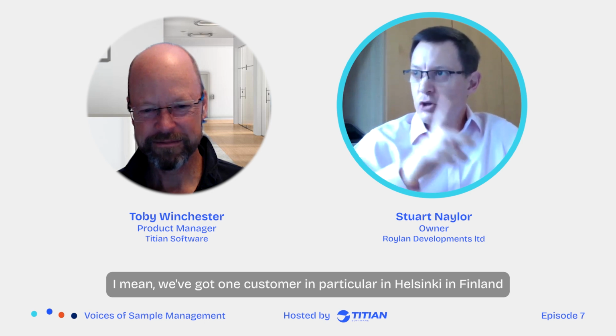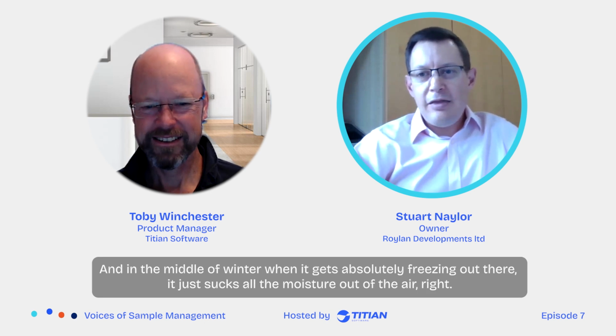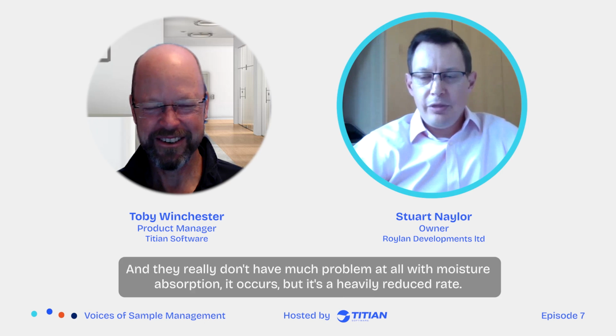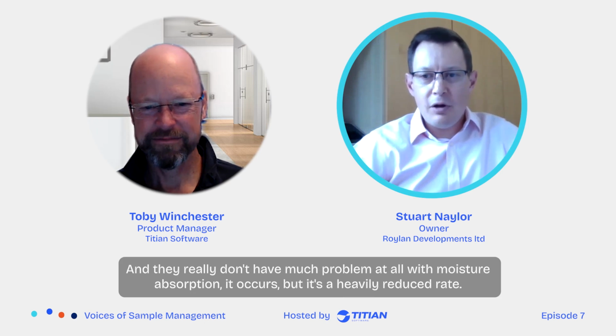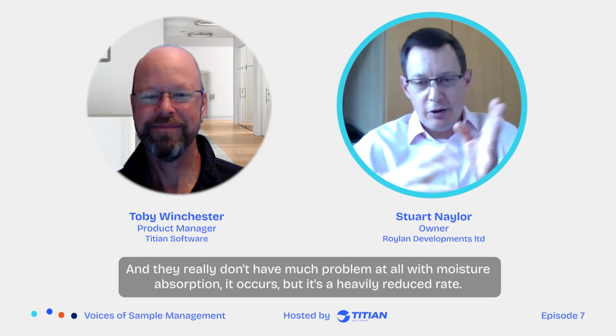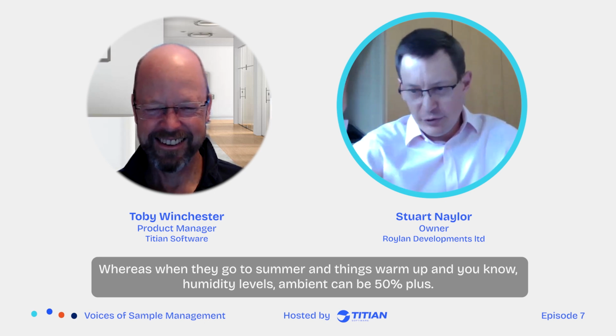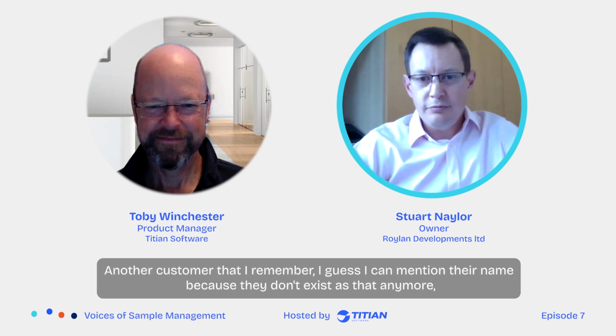We've got one customer in particular in Helsinki in Finland. In the middle of winter, when it gets absolutely freezing out there, it just sucks all the moisture out of the air. And they really don't have much problem at all with moisture absorption. It occurs, but at a heavily reduced rate. Whereas when they go to summer and things warm up, humidity levels at ambient can be 50% plus, and they see some quite aggressive moisture absorption.